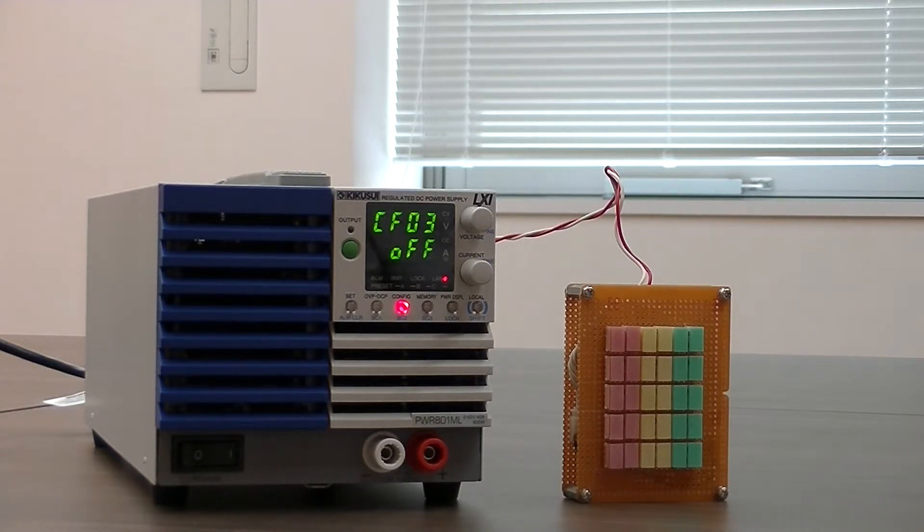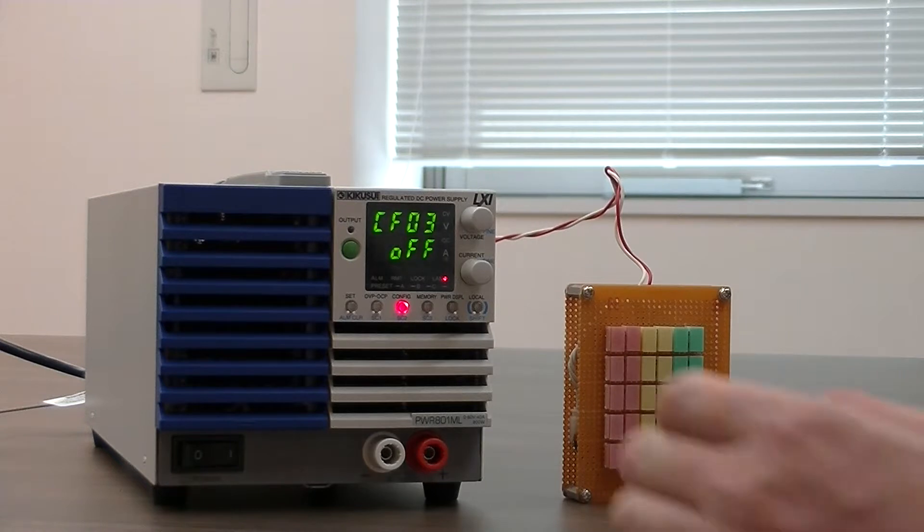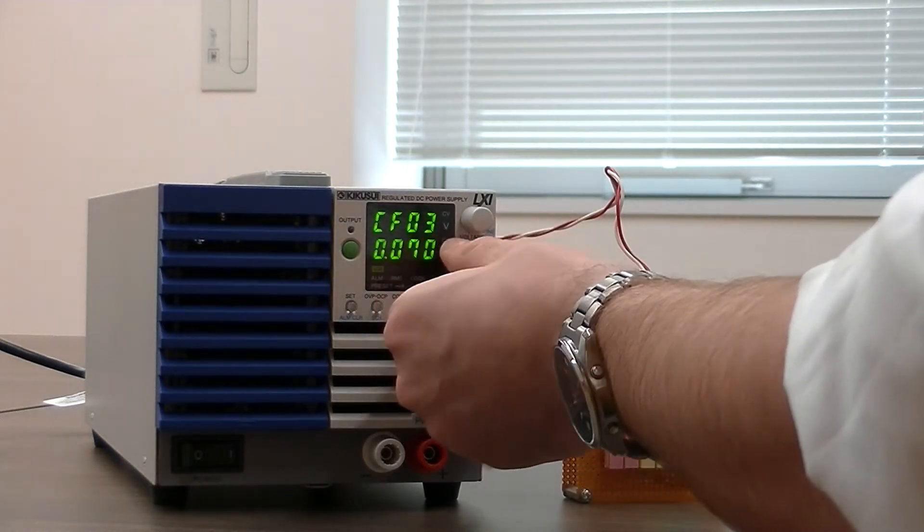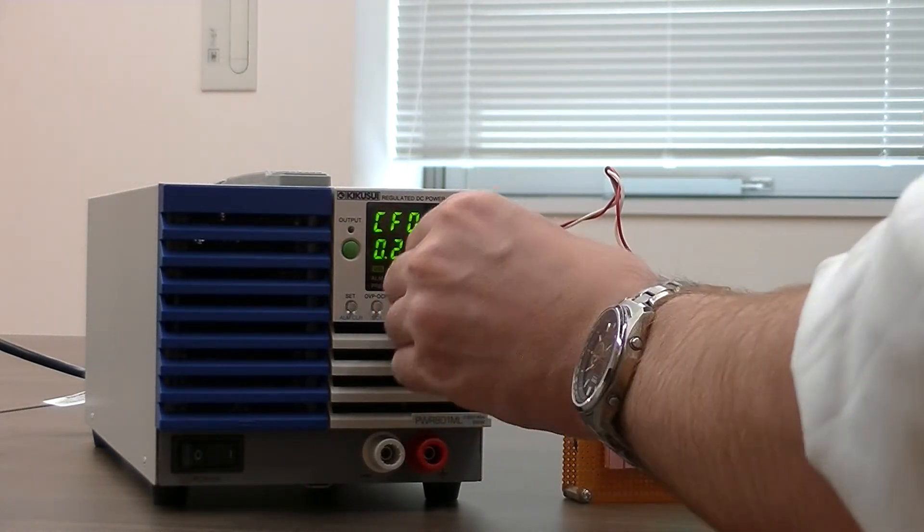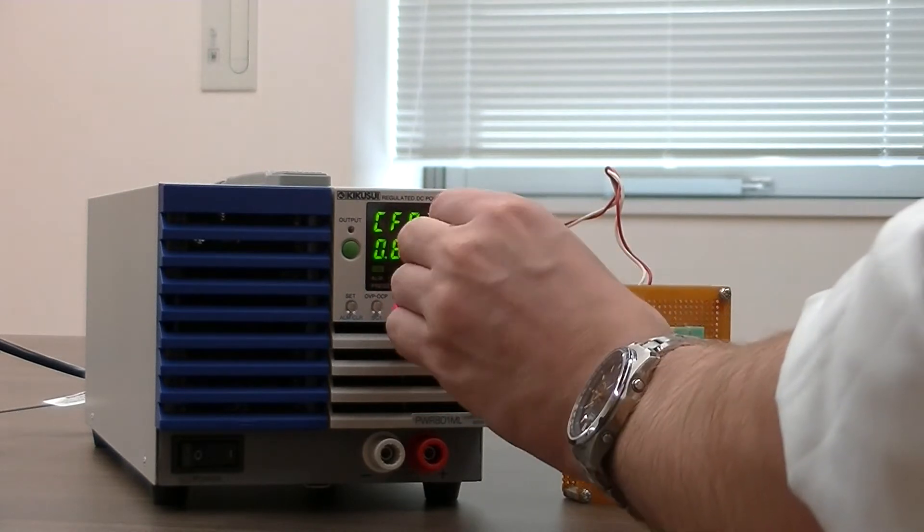The amount of resistance you can apply internally depends on the model, and with this specific model, the PWR-801ML, the maximum amount of resistance is 2 ohms.